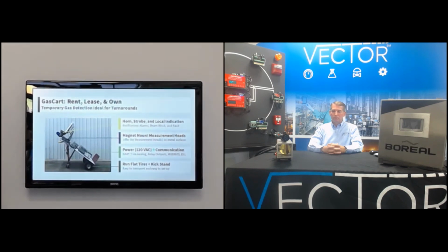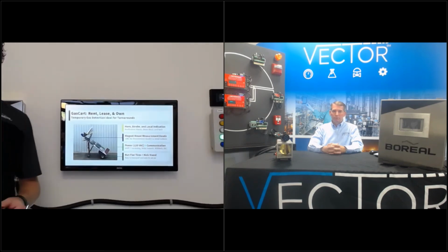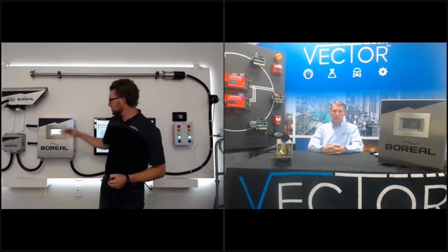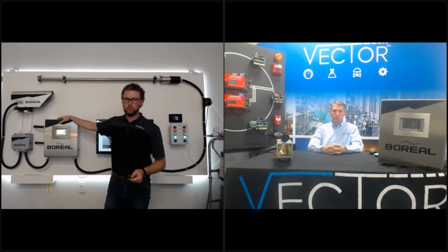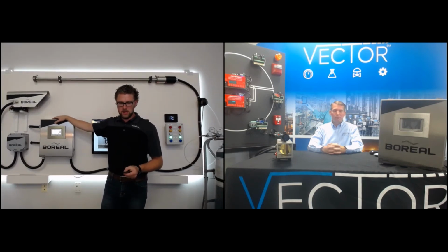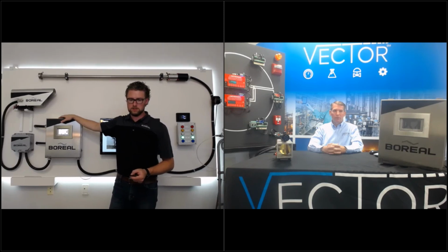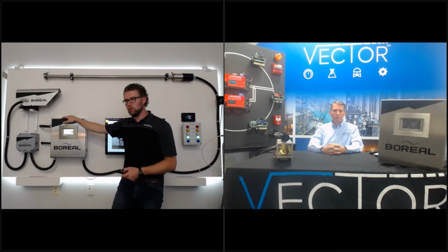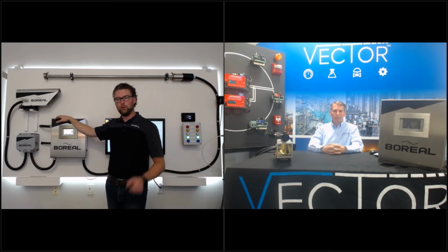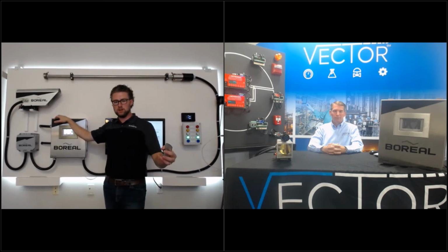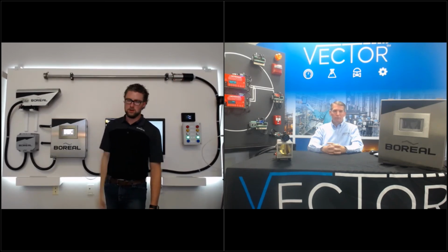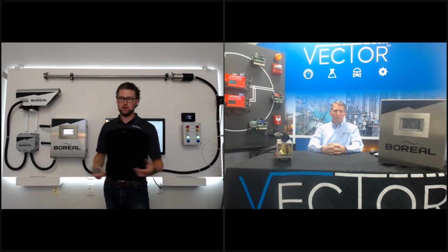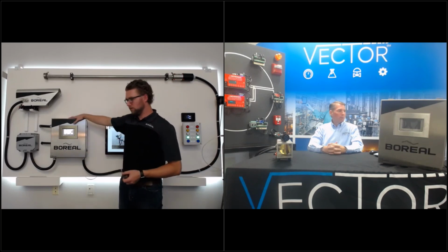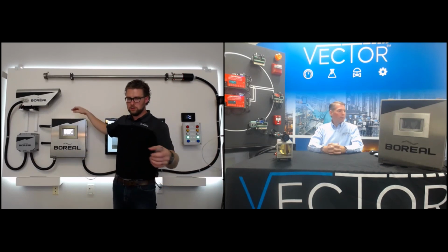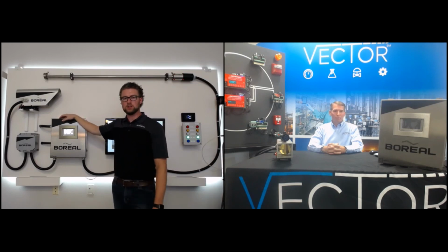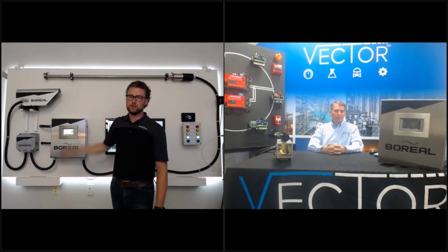Okay, and do these units have wireless capability? Yeah, so with HART 7, which is one of the communication outputs available for this particular product, you can connect to any one of the wireless transmitters or wireless HART networks as well. There are about four or five different vendors that manufacture wireless HART capabilities, and any of those can be used within this particular product. So yes, whether it's fixed gas detection or those portable gas carts, which you have the brochure for, you can have wireless HART communication protocols for this product as well.